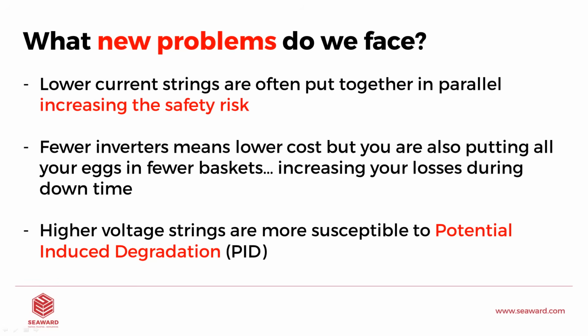And I do suggest that if you're looking for 1500 volt test equipment, you should really look for a high maximum current rating. So for instance, there are other instruments on the market which can IV curve trace at 1500 volts, but they only do it at 10 amps. Now that is not so useful to us, particularly if we're dealing with combiner boxes.